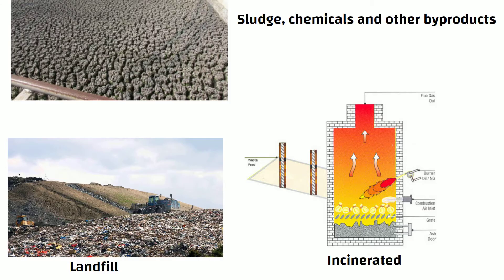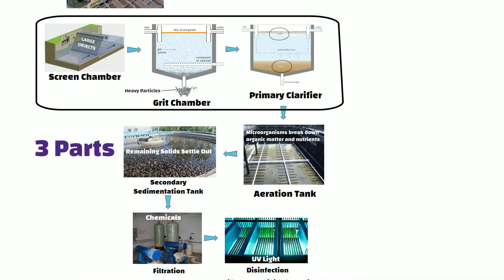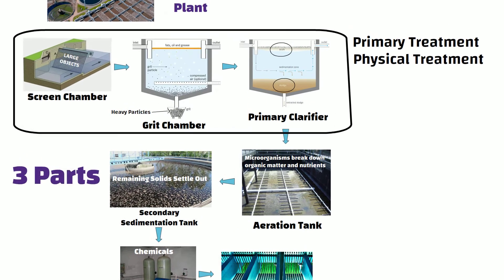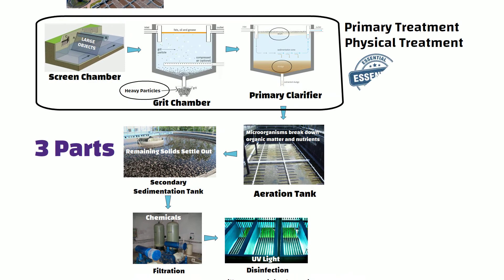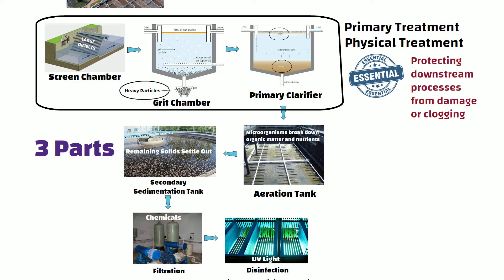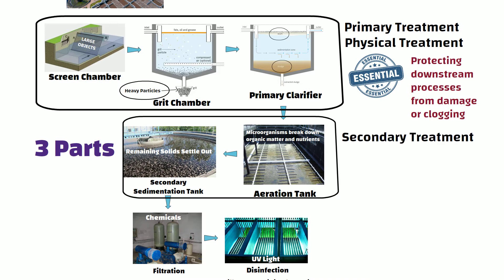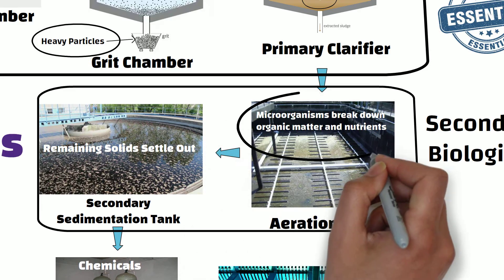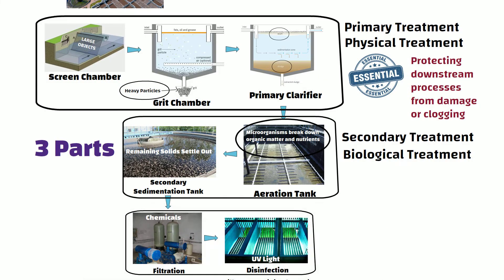This whole process is divided into three parts. From screening to primary clarifier, it is called primary treatment or physical treatment, where large and small solid particles are removed from the waste water — this is essential in protecting downstream processes from damage or clogging. From aeration tank to secondary sedimentation tank, it is called secondary treatment or biological treatment, in which microorganisms break down organic matter. Filtration and disinfection come under tertiary treatment, also called chemical treatment.